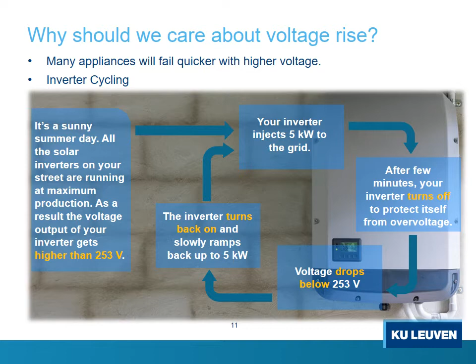I hope it's now clear what the voltage rise and voltage drop problems are, and why it is important to have a control system or some active elements to control voltage between maximum and minimum limits. Solutions to solve the voltage rise and voltage drop problems can be classified according to the following 3 categories. Solutions that are implemented within the grid operator infrastructure, such as network reinforcement, for example, increasing the size of the feeder to reduce the total resistance of the network, that is, to reduce the voltage drop. On-load tap changer, that is, to change the voltage of the transformer dynamically.